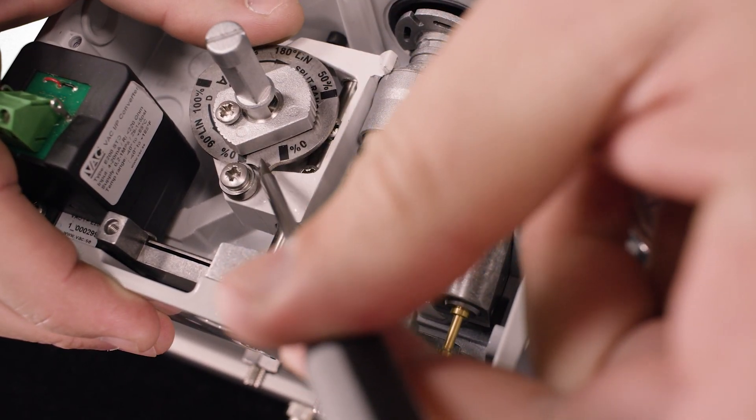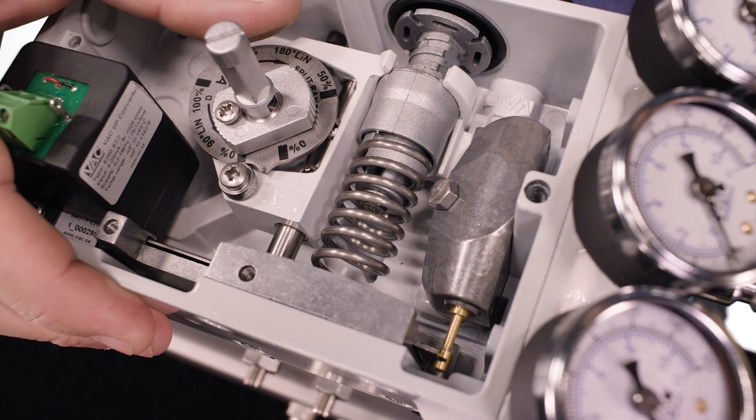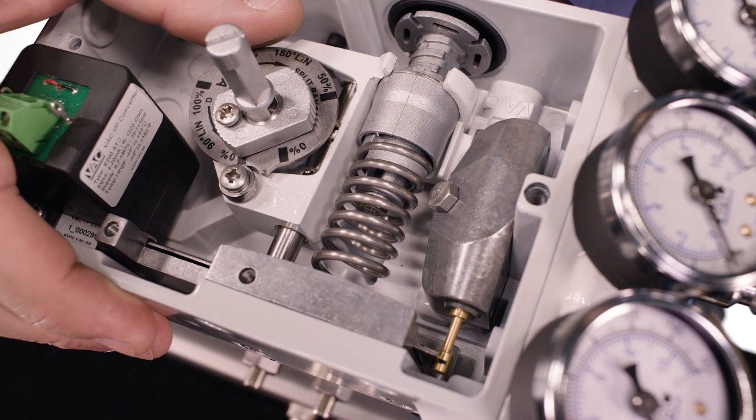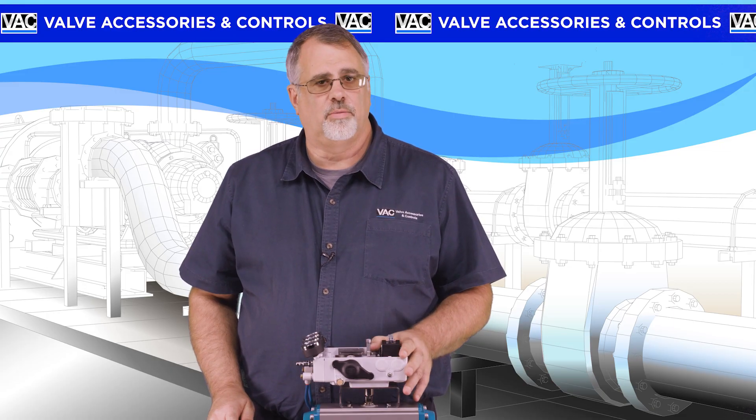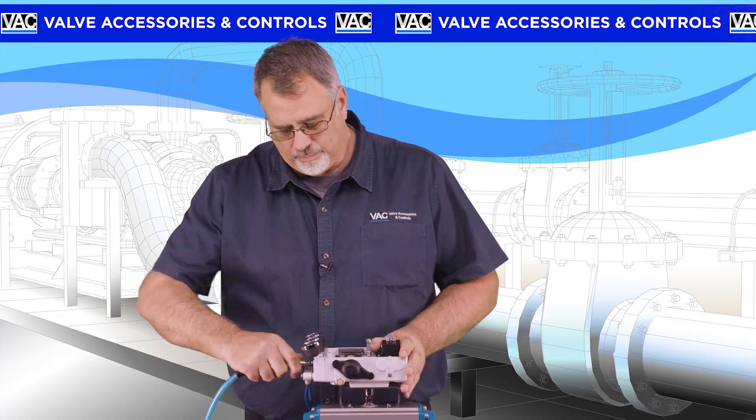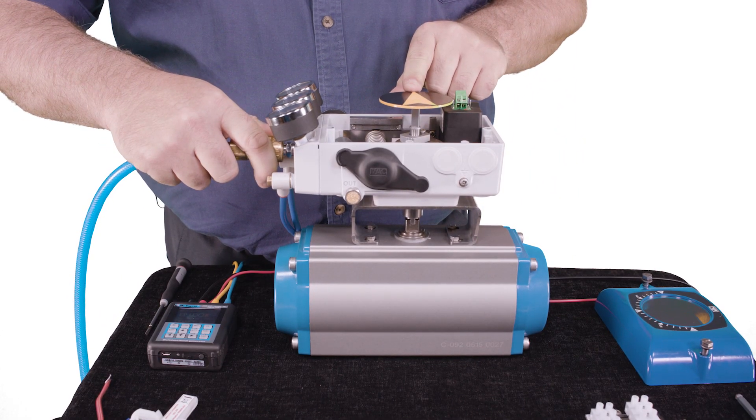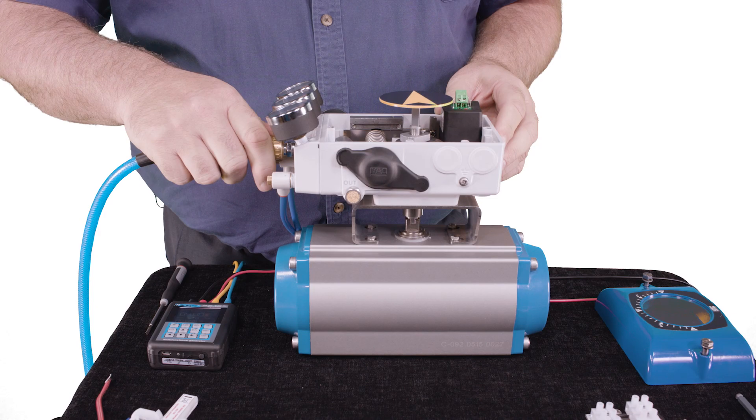If there is a small gap between the tip of the cam and the bearing, then the cam is set correctly. Now we can apply air to the positioner's supply port. If the positioner is tubed correctly, the valve will not move when the air is applied.